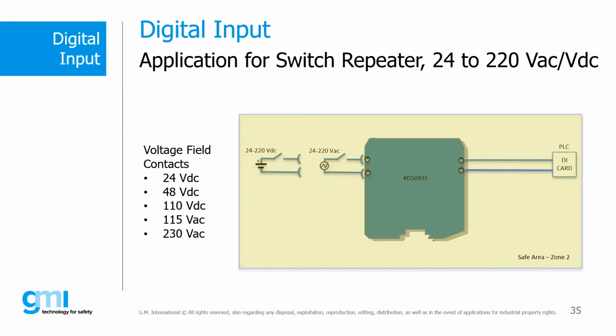To deal with this problem, GMI has equipped most of the relays of the new D5000 series with gold plated contacts to make them suitable for this particular application. In addition, GMI has developed a universal device able to receive at its input different voltage levels, selectable via switch, while the output provides a voltage-free optocoupled contact compatible with all PLC DCS systems, which ensures maximum conductivity even at lower currents. This device is specifically designed to work in this kind of application where we have to communicate between two systems distant from each other, or where we have to signal to a system the presence or absence of voltage.